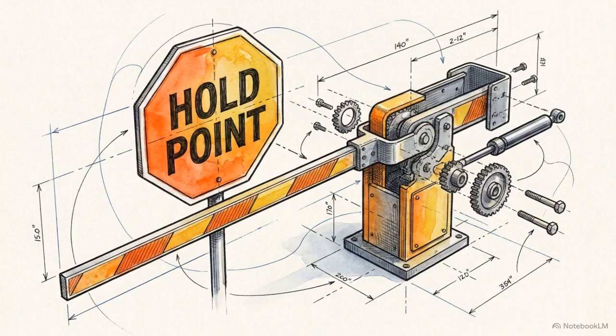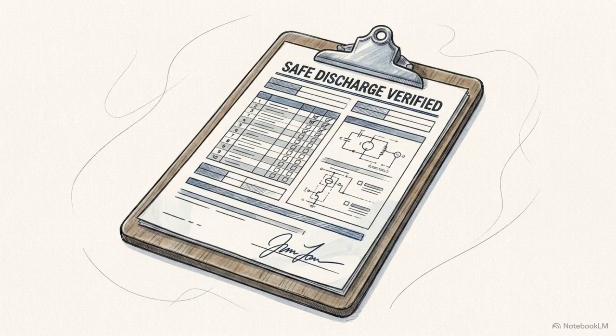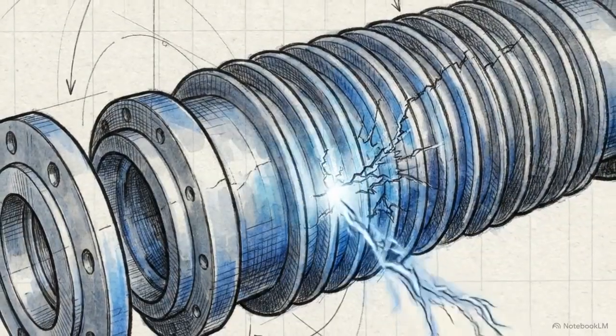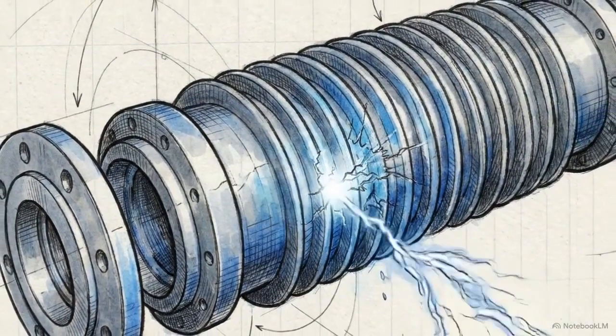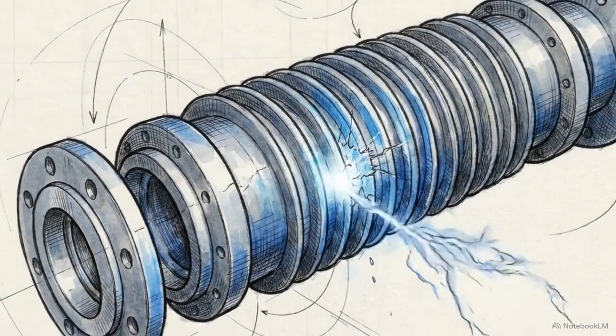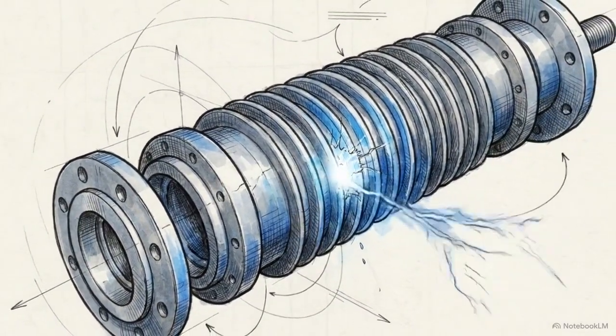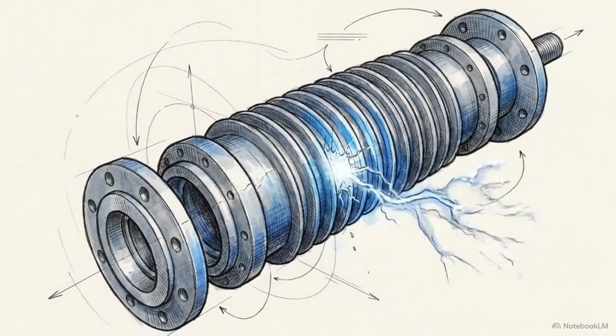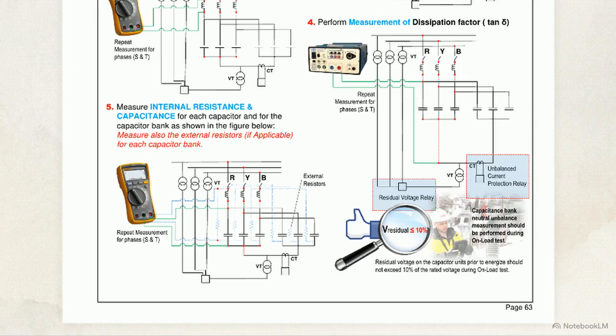The transition from Step 8 of the first script to the live testing sequence is marked by a mandatory hold point. A witness must verify the accepted results and sign off on safe discharge status before proceeding. Energizing a capacitor while it holds a DC charge creates high-magnitude transient overvoltages. This can cause immediate equipment failure and risk to the substation. To mitigate this, the framework mandates residual voltage decay to 10% or less of the rated voltage before re-energization.